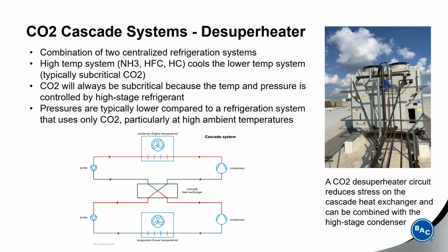low stage CO2 system. This cascade type system is popular in areas of warmer climates with higher ambient temperatures, because it allows them to ensure subcritical operation of the CO2 system. Typically, there's just a single HFC condenser, and many times designers will include a CO2 desuperheater in terms of an air-cooled condenser or cooler located between the CO2 compressor discharge and the cascade heat exchanger. This desuperheater is meant to reduce the load and size needed of the heat exchanger and also reduce some of the thermal stress of the superheated CO2 entering that heat exchanger.